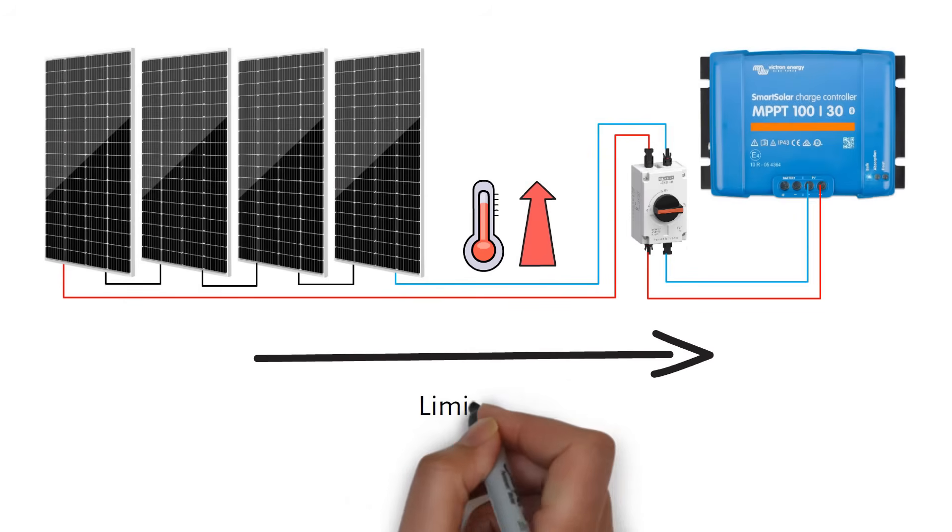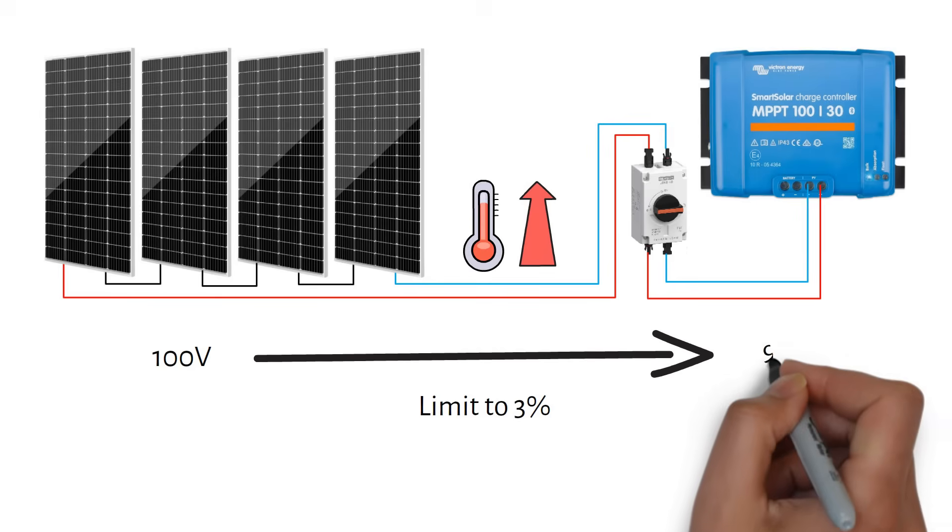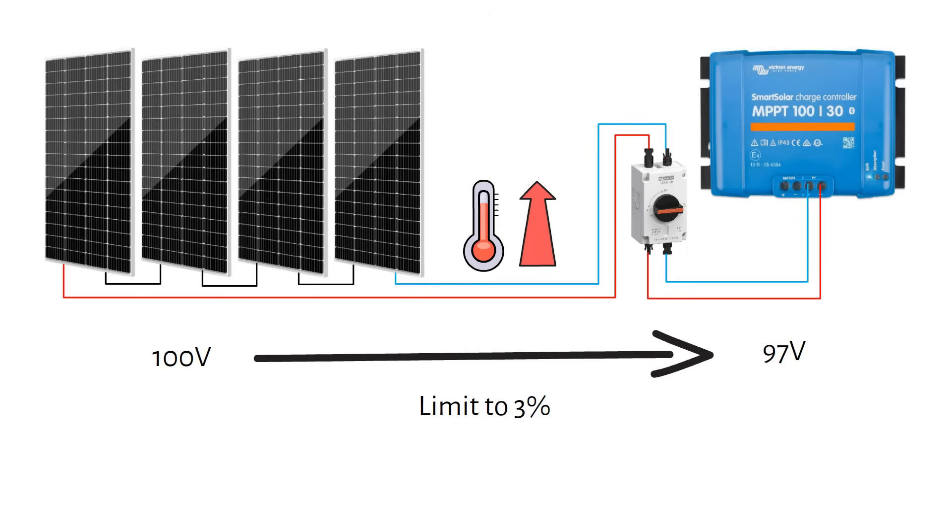We limit the voltage drop to 3%. For example, if your string of panels is 100 volts, 3% means you can lose about 3 volts along the cable, leaving you with 97 volts at the end. If the current is 10 amps and the loss is 3 volts, then we have a total power loss of 30 watts.